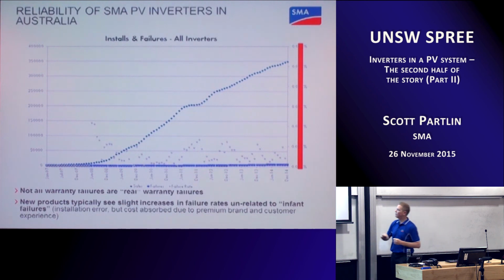And you can see, they're plotted on this axis over the left-hand side. There's a lot of inverters out there, and there's not a lot of them that have failed. And then I've got this scatter graph going on as well, which is just showing the month-to-month variation in the total failure rate for the fleet of inverters. And typically what you find is that, as pointed out by the Sun Edison data, all of their failures added up to about a 1% energy loss, and so the inverters therefore are responsible for maybe a little bit less than 0.5% of a plant's energy loss throughout the year.